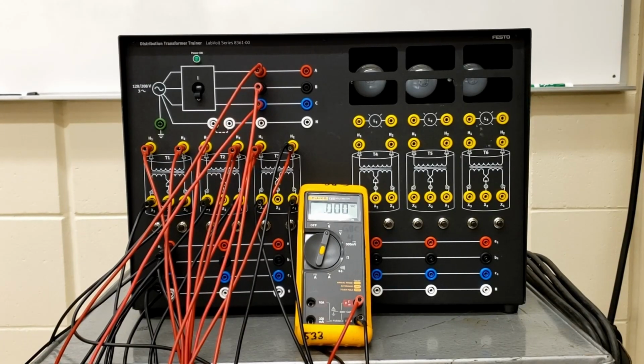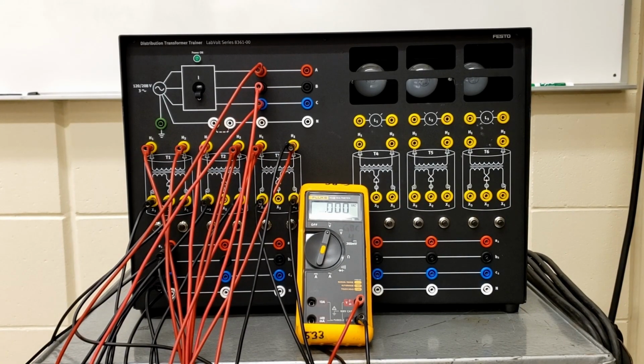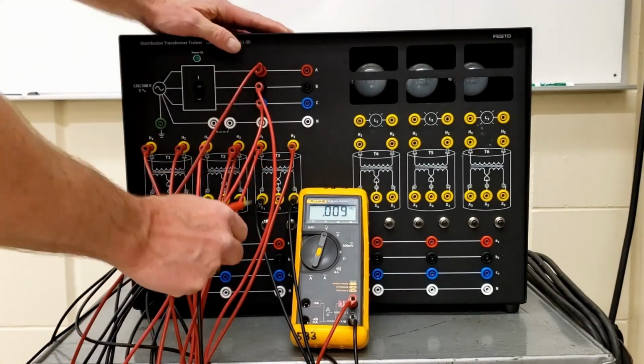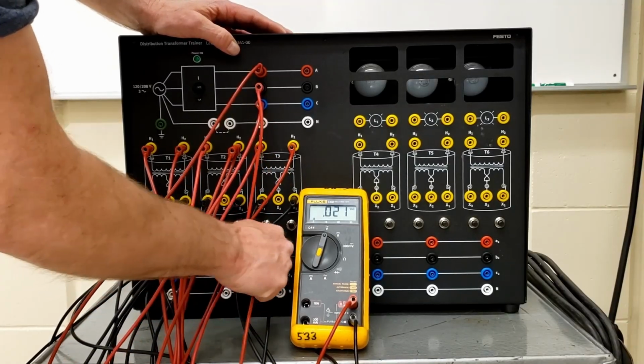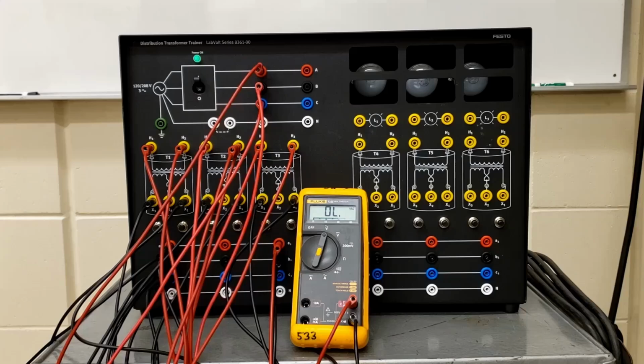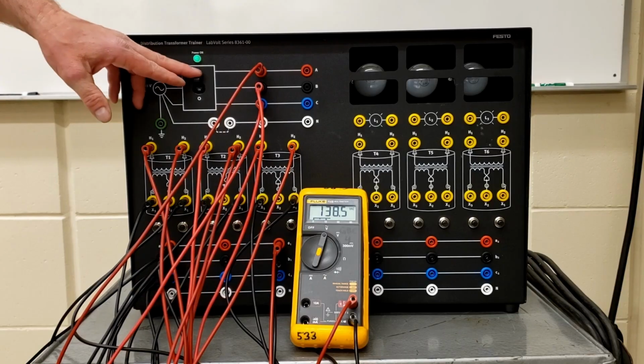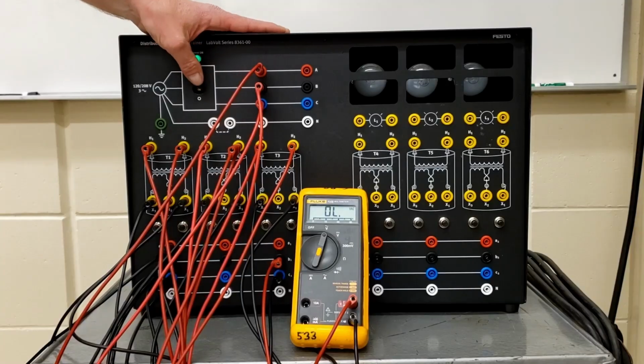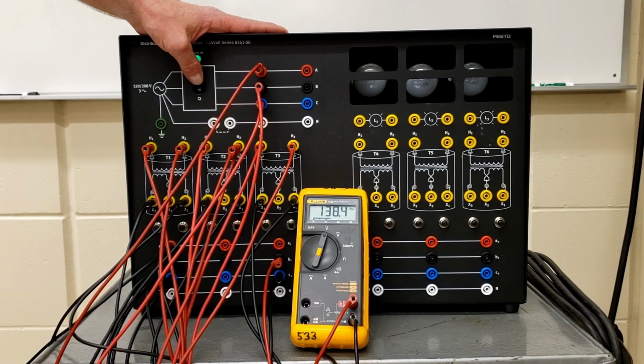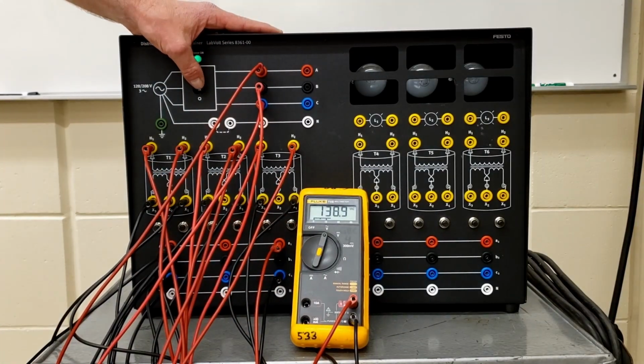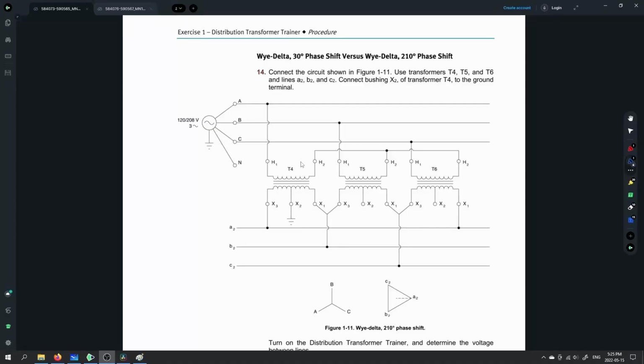So determine the voltages between lines A1 and B1, B1 and C1, C1 and A1. Okay, so we're going to take this guy off. We're going to look at the voltage between A1 and B1. So we got 138 volts between those guys. Okay, and we should have equal voltages between everything. So between B and C, we should also see 138 volts. Okay, which we do. And between C and A, we should see 138 volts as well. Excellent.